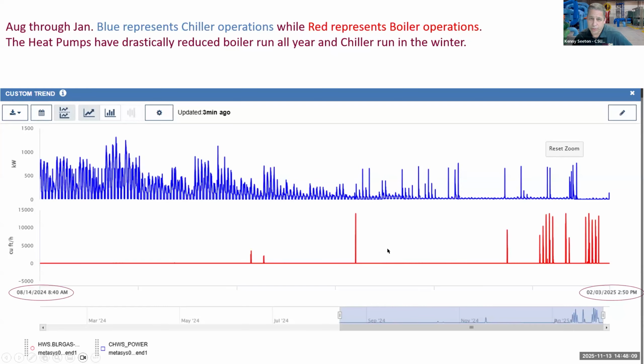The real data: when the heat pumps are running, the boilers aren't. In the graphs that we see here, the red is gas usage and the blue is chiller electricity. And so in the wintertime, when the heat pumps are running really hard, the chiller plant is slowing down also, which was a really huge, bigger benefit than I thought we would see.